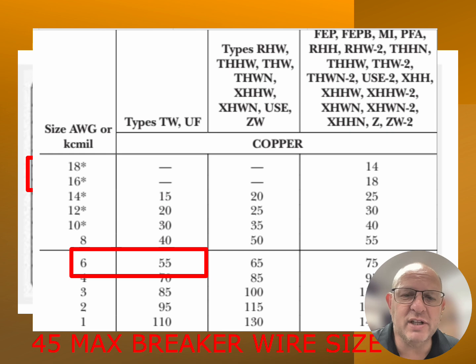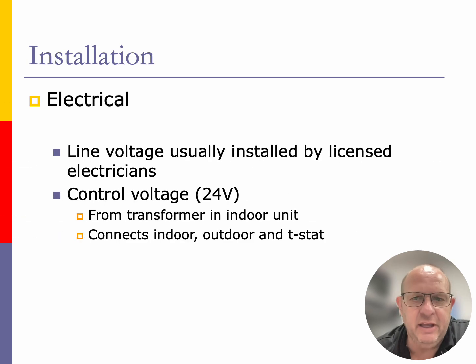But in most cases, most of our air conditioning systems that are out there will give us minimum and maximum breakers and amperages that we can use on those particular units. And then we will know what size wire and what size breaker to install based off that. If we don't, this is the process that we have to typically use. High voltage electrical is going to be installed by an electrician. They're going to bring it out to the outdoor unit on a new install, and then we're going to take that system power and hook it up from the disconnect into the unit itself. The control wiring is usually run by the field technician. The field technician is going to take that wire and run it from the indoor unit to the thermostat, and then the thermostat is going to tell the outdoor unit what it needs to do.